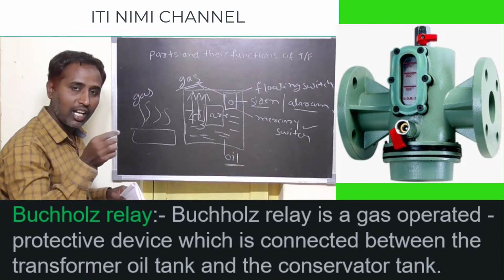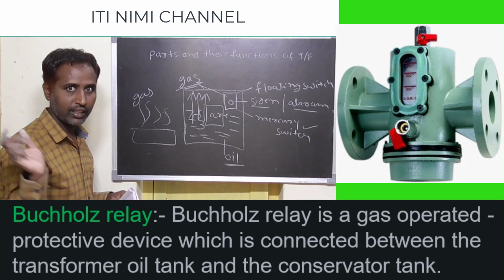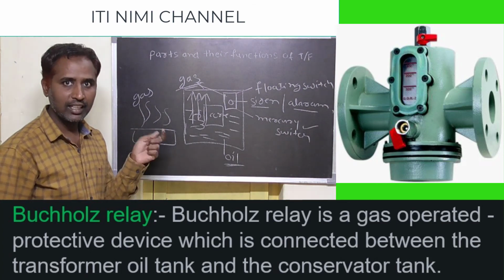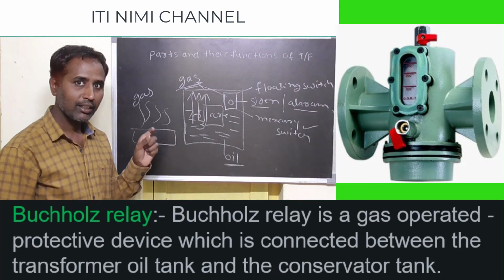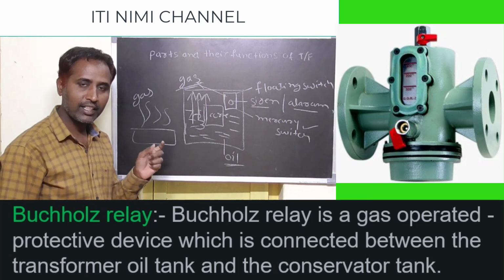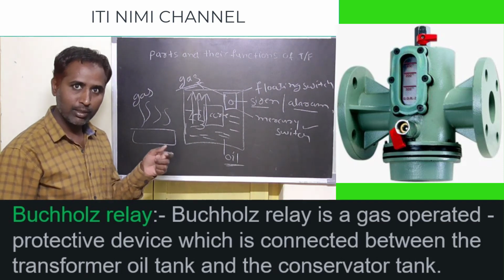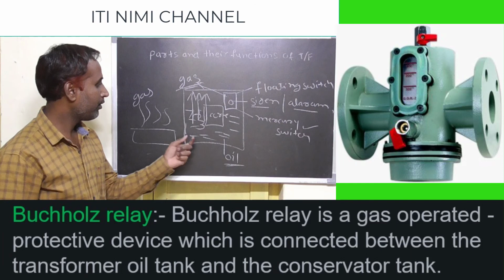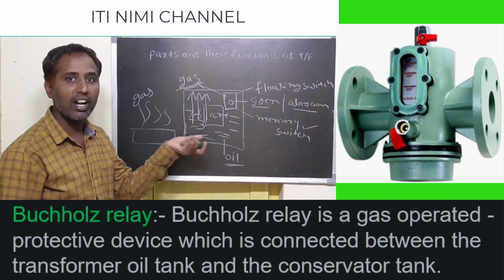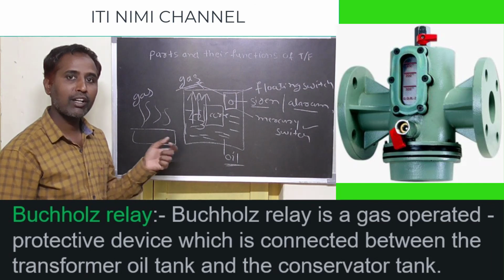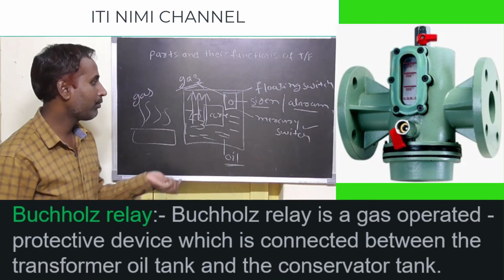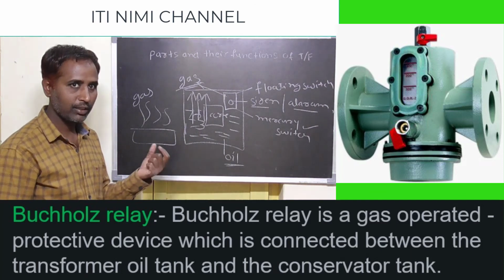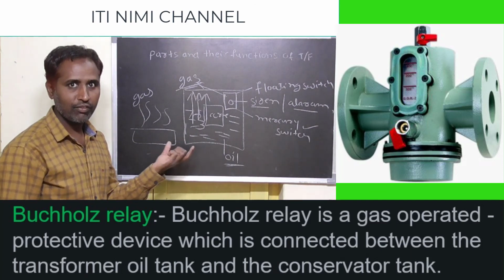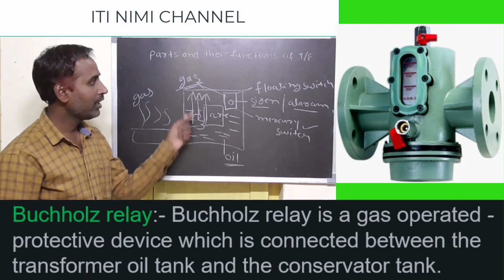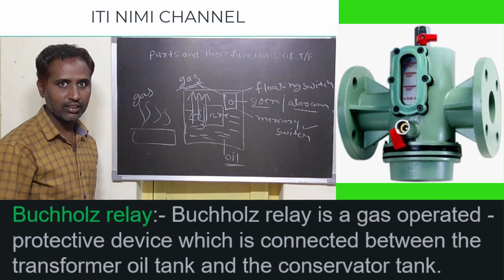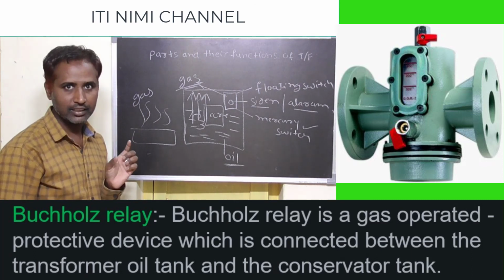Why does it do this? To protect the transformer from further damage - this is the function of Buchholz relay. Buchholz relay is a gas operated protective device; it protects the transformer from heat and from any fault, protecting it from further damage using the floating switch, siren, mercury switch, etc. I think this concept is clear now.